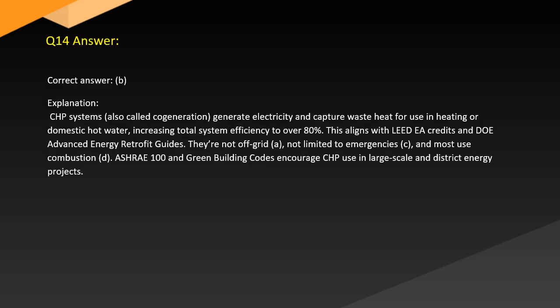Answer. Correct answer: B. Explanation. CHP systems, also called cogeneration, generate electricity and capture waste heat for use in heating or domestic hot water, increasing total system efficiency to over 80%. This aligns with LEED EA credits and DOE Advanced Energy Retrofit Guides. They're not off-grid (A), not limited to emergencies (C), and most use combustion (D). ASHRAE 100 and green building codes encourage CHP use in large-scale and district energy projects.